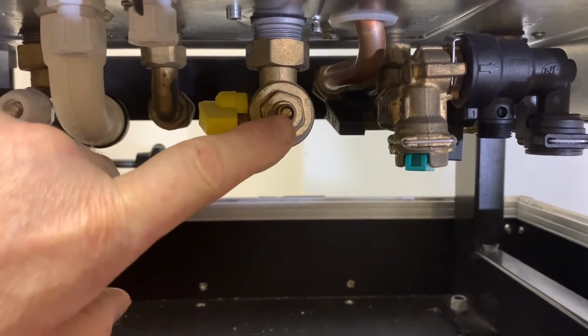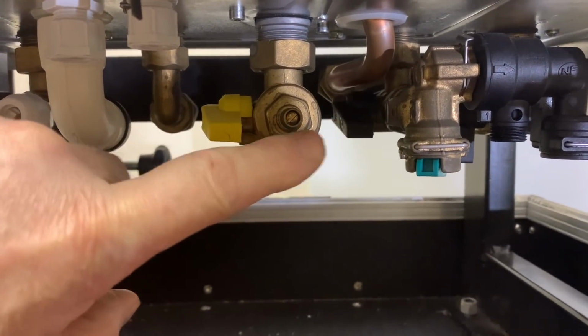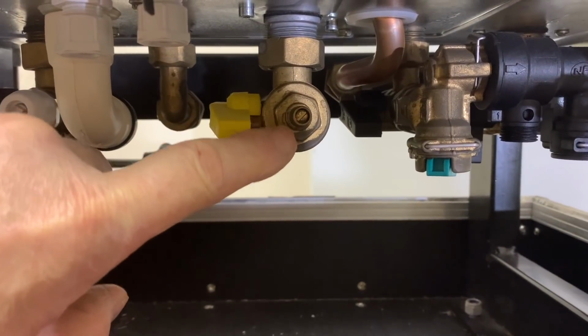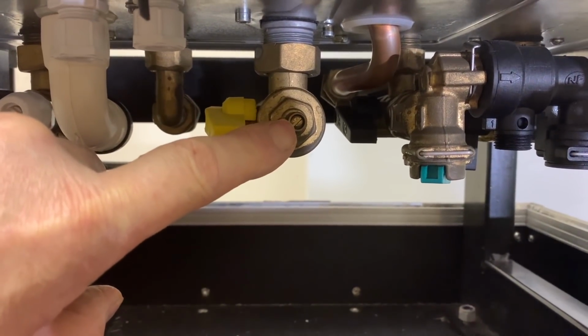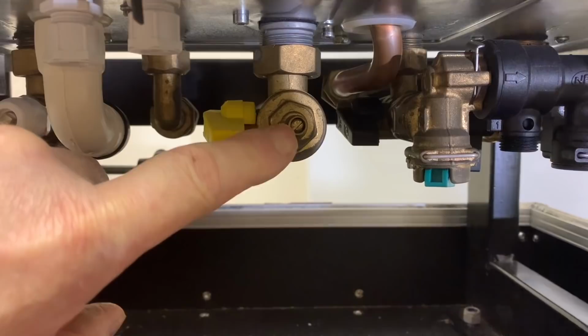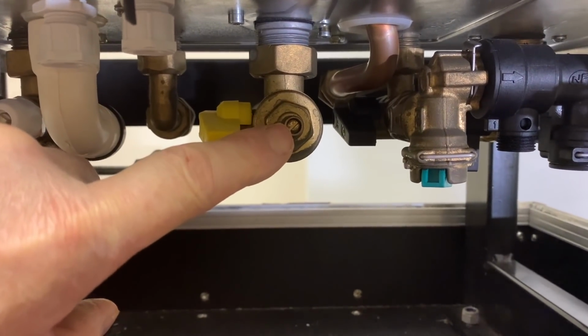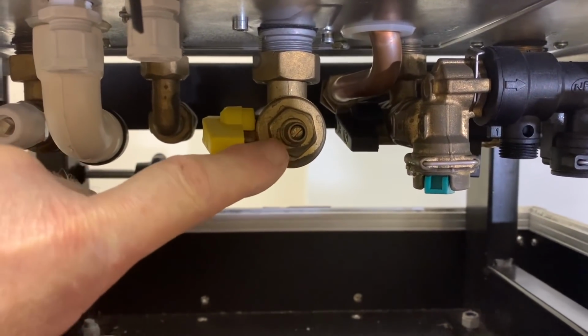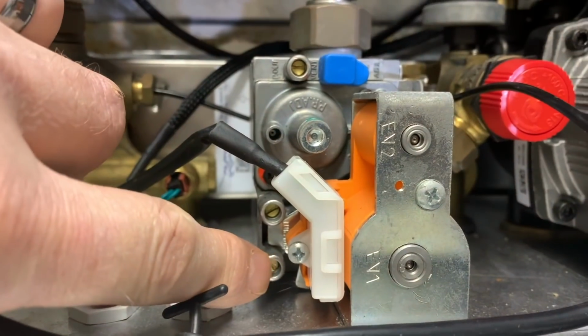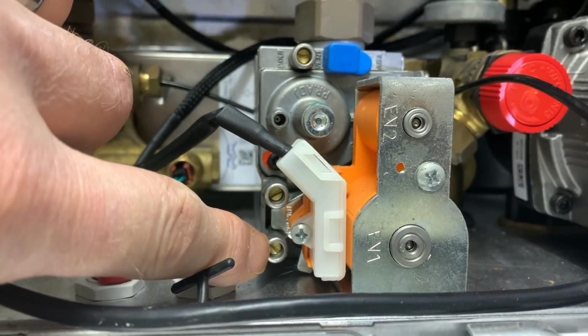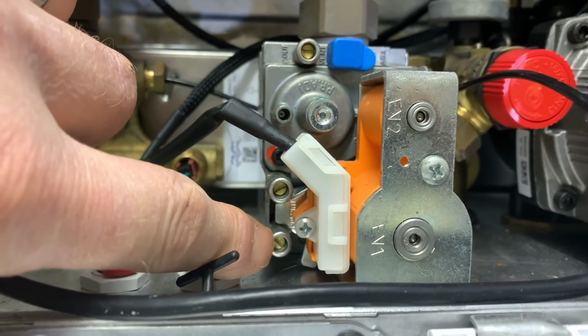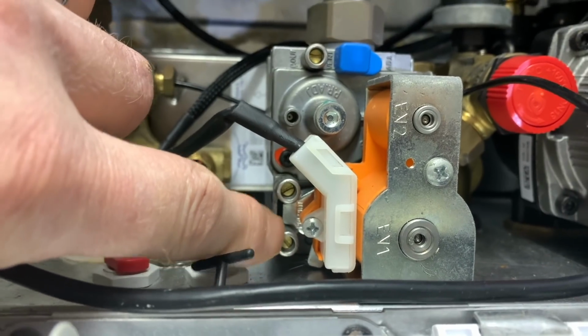On the gas connection here there is a test nipple, and on this test nipple we need no more than a 1 millibar drop from our meter. We need an inlet pressure here of between 18 and 22 millibars. If we look on the gas valve quickly, we've got our inlet test pressure here, and Baxi say they want at least 17 millibars here.